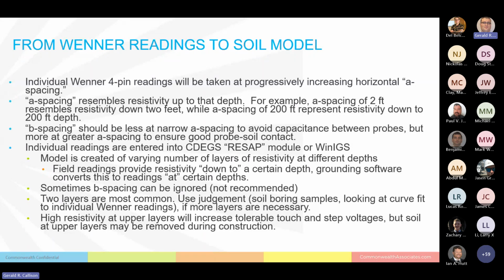So basically, we've got all these different readings at different horizontal A spacings, and we're going to enter those readings into the CDEGS RESAP module or into WinIGS, the two major grounding software packages we work with at Commonwealth. And then we're going to create a model of varying numbers of layers of resistivity at different depths, 100 ohm-meters down to 10 feet, 200 ohm-meters below 10 feet, for example. In the field, and again, this is key, the field readings provide resistivity down to a certain depth, but the grounding software converts this to readings at certain depths.